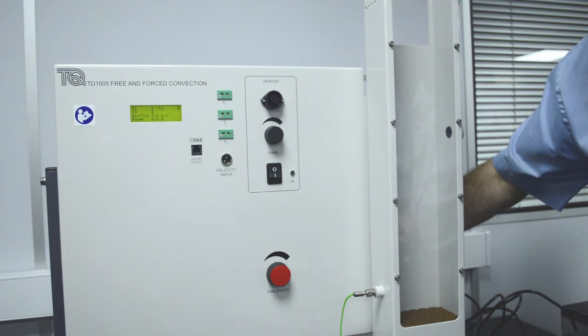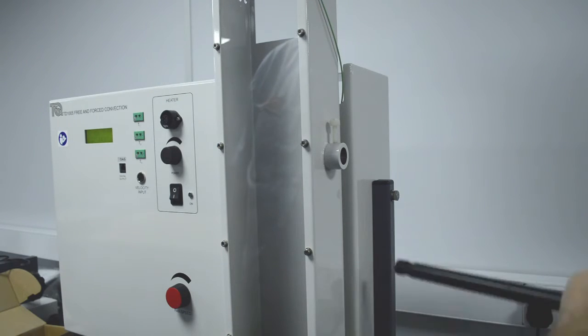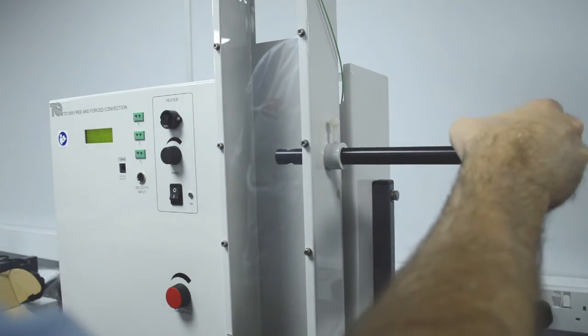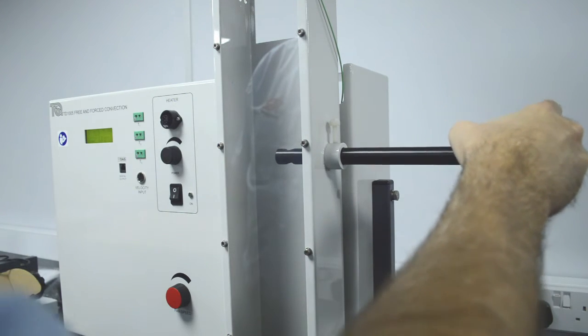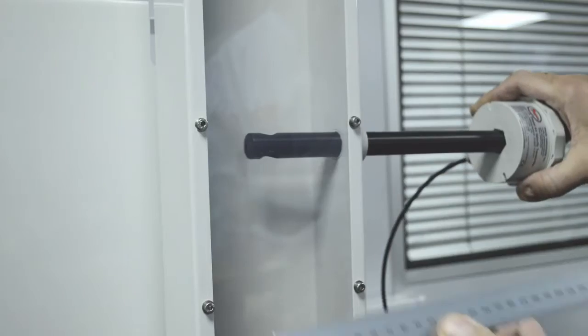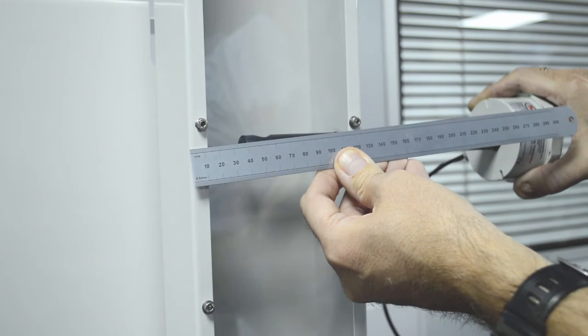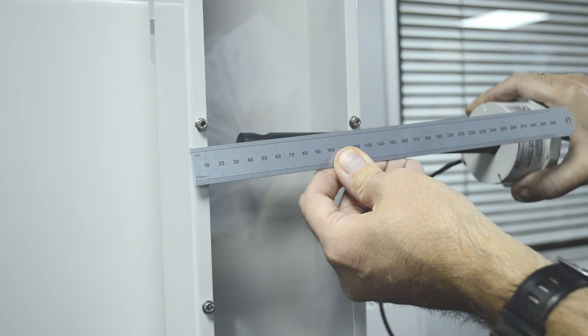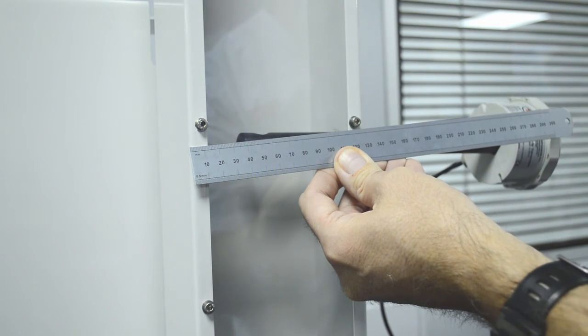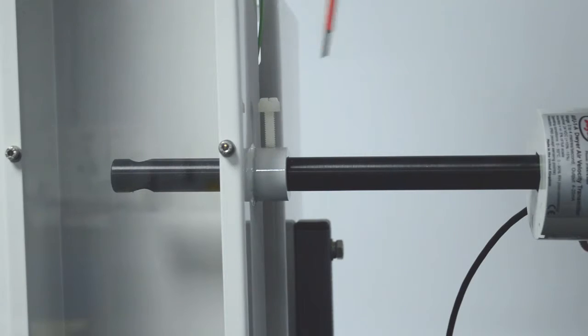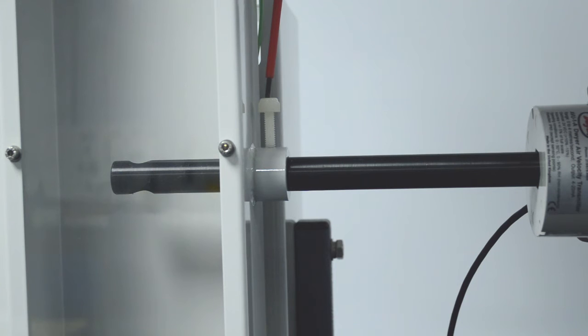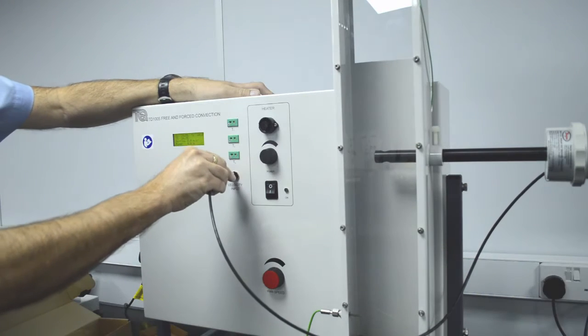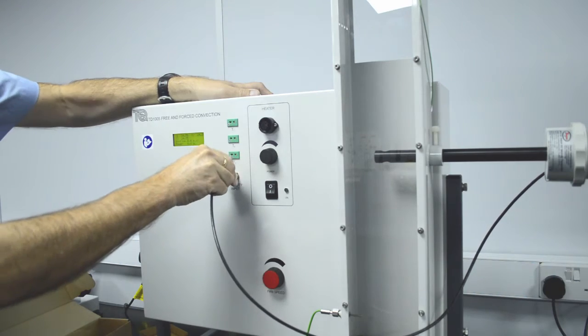Carefully push the anemometer probe into its socket on the side of the duct so the hole in its tip is in the middle of the duct. Rotate the probe so its hole aligns with the airflow and then tighten up with a screwdriver. Plug in the anemometer on the front panel.